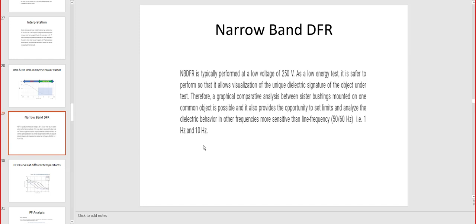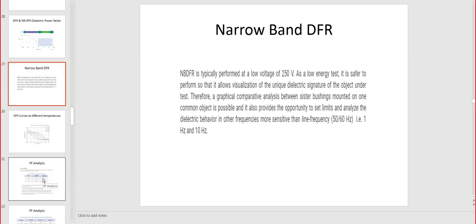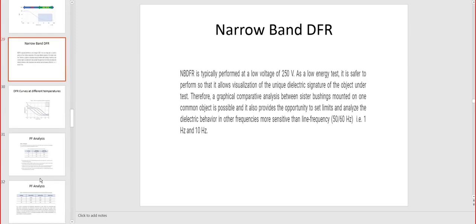Eventually you have some data from the manufacturer that they did for the factory acceptance test. Those will serve from the bulletin. They will serve as an initial starting point for the graph. Again, the three phases should be pretty close to each other for the same bushing types. And yes, we don't install different manufacturers on different phases. We will have all the same.